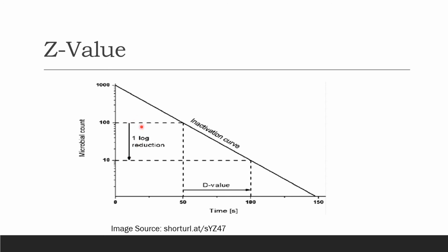This log reduction is the Z value. For heat treatment, a D value only refers to the resistance of a microorganism at a particular temperature. To obtain the influence of temperature changes on thermal resistance, a relationship between temperature and log D value can be developed, leading to the expression of a Z value.